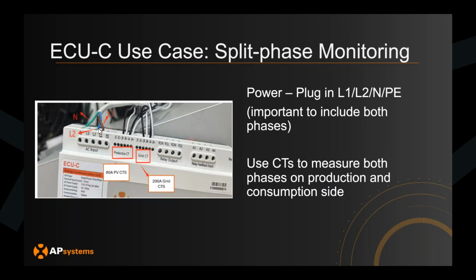Also important: to power the ECU-C, you need L1 and neutral to have voltage across it. If you want to measure power on both phases, remember power is a function of current and voltage. Current comes from the external CTs, but to measure voltage, you need this plug. So when doing split phase consumption monitoring, make sure to plug in L1 and L2 to get voltage readings from the ECU-C.